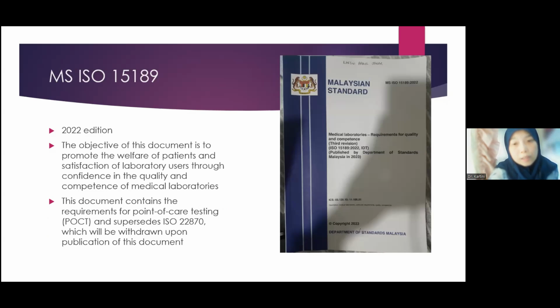So the Malaysian standard for ISO 15189 in the 2022 edition, which was published in 2023, actually states the requirements for point-of-care testing, and this supersedes the ISO 22870, which will be withdrawn upon publication of this document.